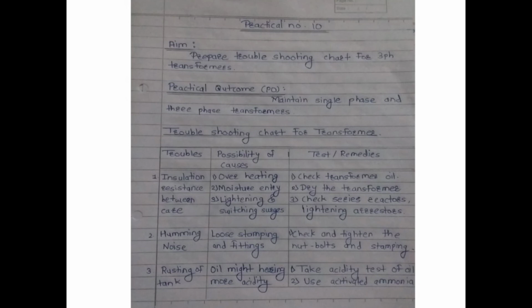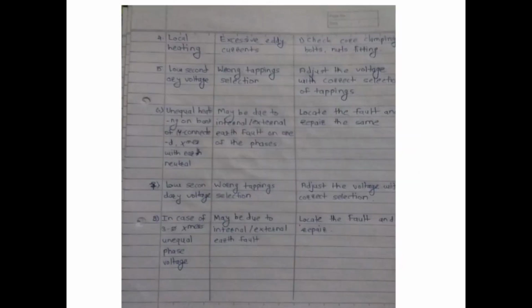Then third is rusting of the tank. Possible causes are that the oil might have more acidity, and tests and remedies are to take an acidity test on the oil, and second, use activated alumina. Fourth is local heating. The cause is excessive eddy current, and remedies are to check the core clamping and bolt fitting. Fifth is low secondary voltage. The cause is wrong tapping selection. The remedy is to adjust the voltage with correct selection of tapping.